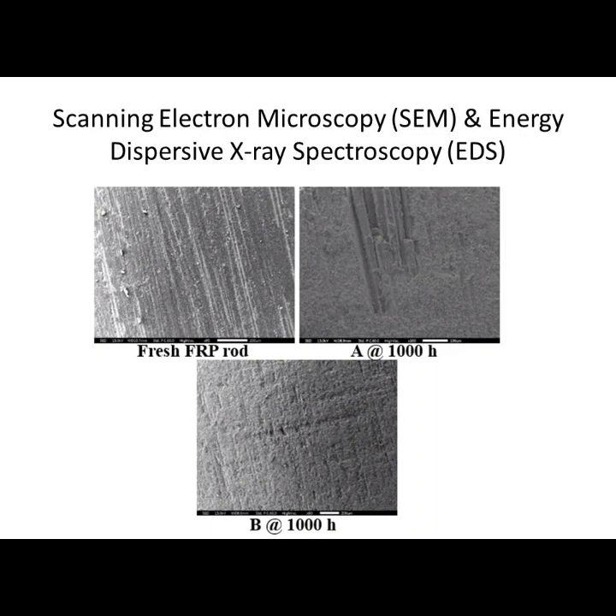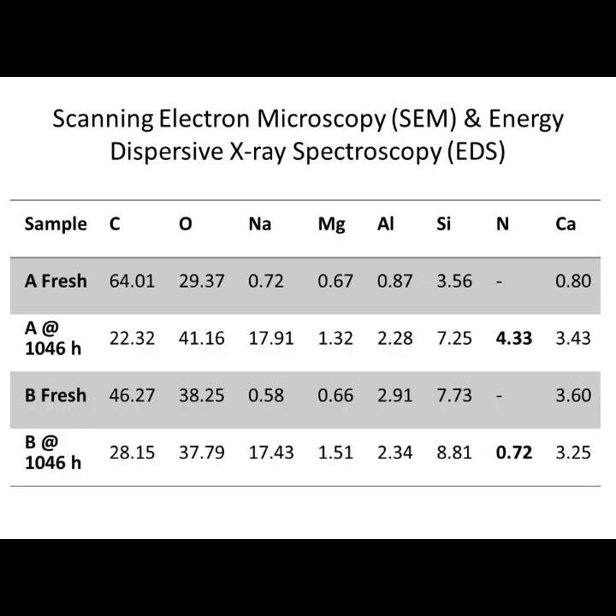However, the newly developed tracking resistant FRP rod shows a superior performance and less degradation, where the glass fiber is still covered with the epoxy resin with a slightly more rough texture. So this table now shows the atomic elemental composition on the surface of the FRP rod samples, both fresh and aged. As we see here, in the normal FRP rod sample a significant decrease in the carbon content is seen, and a significant increase in the oxygen content also is seen, which could be due to the oxidation process taking place under the impact of the electrical discharge, leading to the decomposition of the epoxy resin into water and carbon dioxide, and leading to this significant decrement in the carbon content.